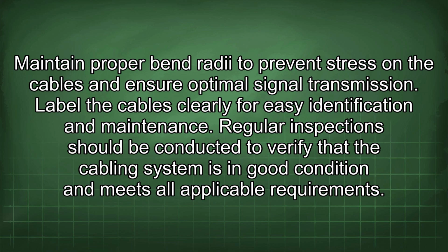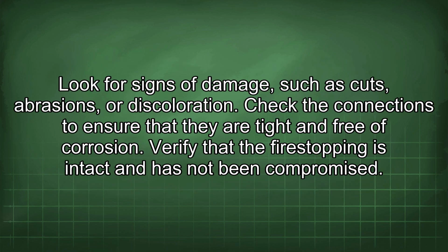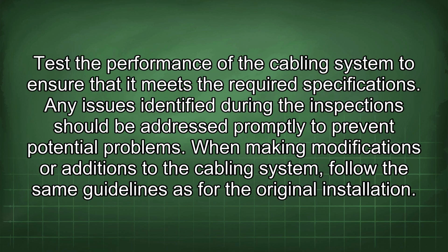Regular inspection should be conducted to verify that the cabling system is in good condition and meets all applicable requirements. Look for signs of damage, such as cuts, abrasions, or discoloration. Check the connections to ensure that they are tight and free of corrosion. Verify that the firestopping is intact and has not been compromised. Test the performance of the cabling system to ensure that it meets the required specifications. Any issues identified during the inspection should be addressed promptly to prevent potential problems.